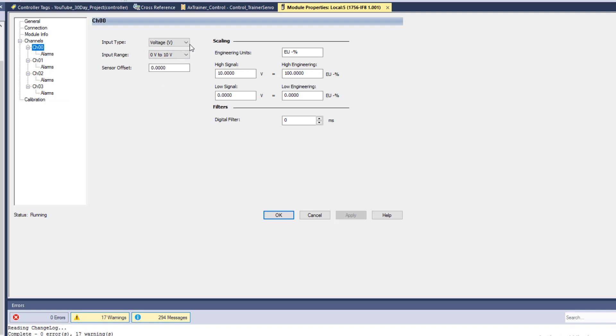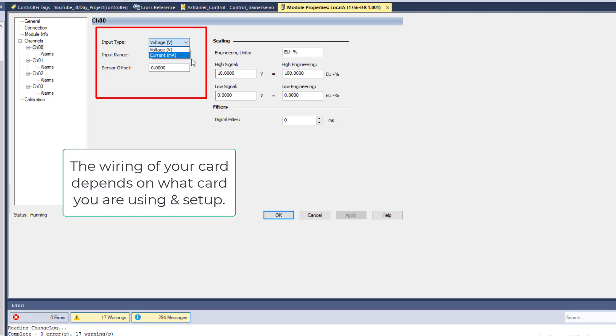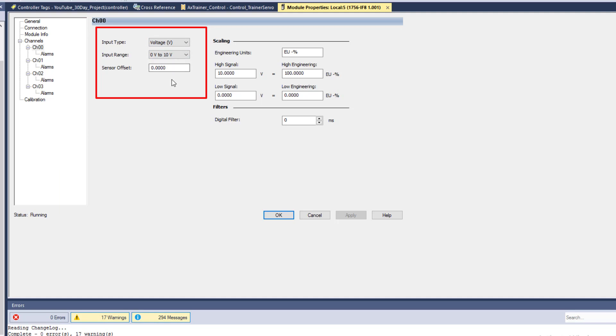This card — and your card may be different — lets you change your inputs and scaling. You can switch from voltage to current, but keep in mind that changing from voltage to current means you would also have to change the wiring on the terminal block of that specific card. I'm going to talk about voltage first and then come back to current.